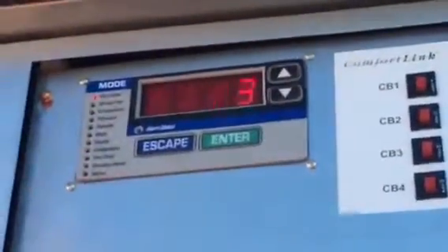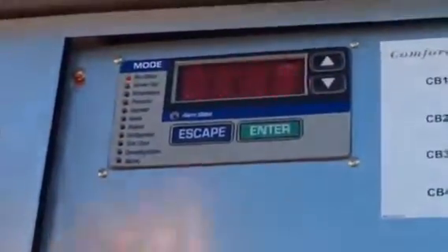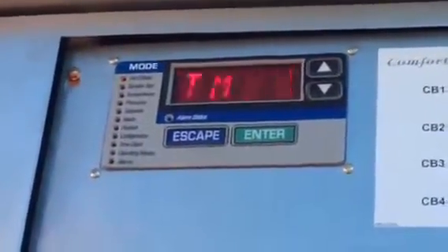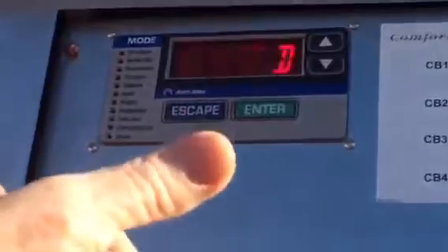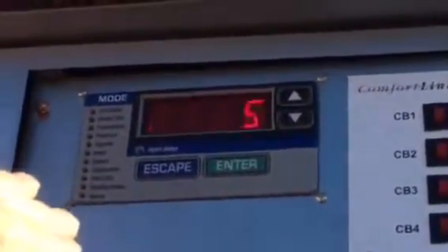So starts and run hours is a nice clue for us doing maintenance to see what's going on with the machine, how it's set up. Time guards, TMGD for time guards is a location within run status. It's going to tell us this compressor is going to start in 4 minutes or 3 minutes. It gives us the timing about what's going to happen. The current temperature below limit. That's the T304. Yep. Oh, you know? Because I pressed enter and escape and it explained it to me.